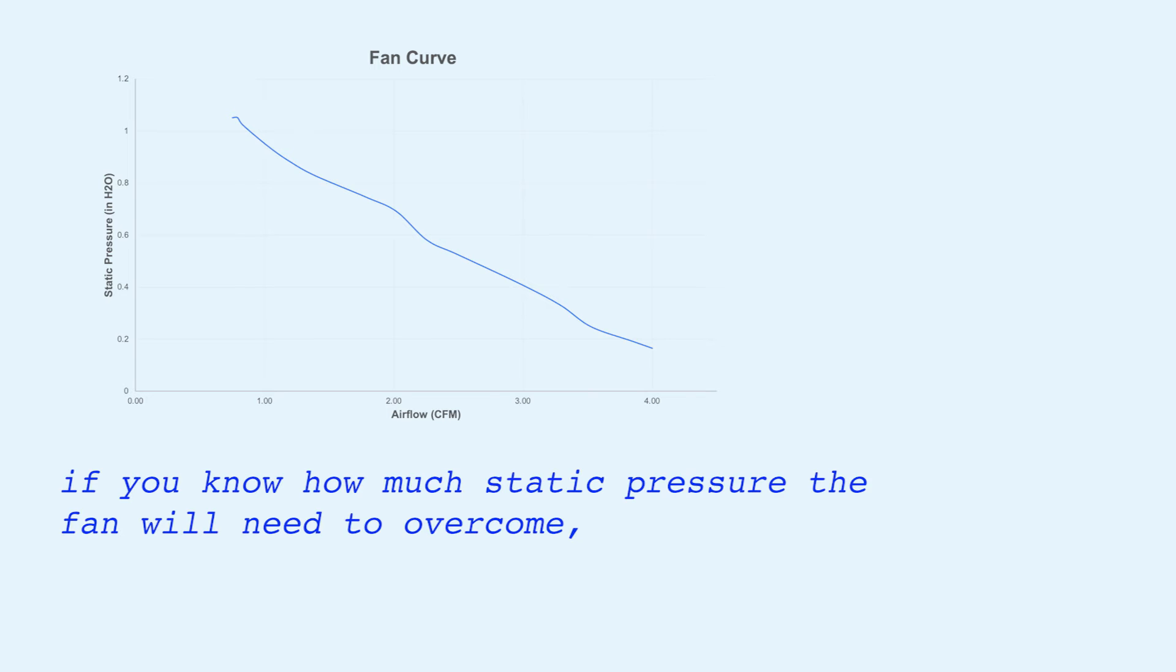Are you starting to see just how powerful the fan curve is? Basically if you know how much static pressure or resistance to airflow the fan will need to overcome, then you will be able to tell how much airflow the fan will be able to provide.